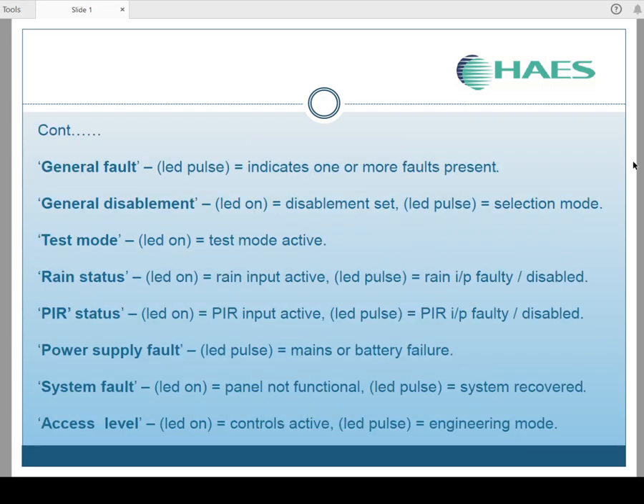Continuing with the LEDs, general fault LED. If the LED pulses, it indicates one or more faults are present on the system. Again, if the general disablement LED is on, it means you've got disablement set. If the LED pulses, it means you're in selection mode within the disablement selector.